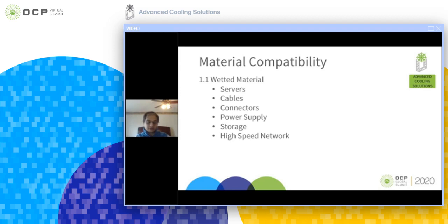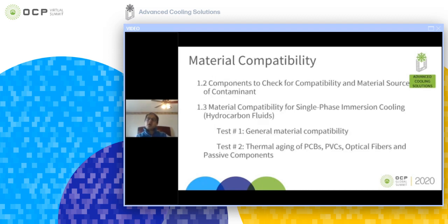And how will it affect the chemical composition? How will it affect the thermal performance? Everything should be covered. We are also talking about the components to check for compatibility and material sources of contaminants. For example, in an air-cooled environment, the effect on the reliability of components would be from the gaseous and particulate contaminants when you use air-side economization or free air cooling.